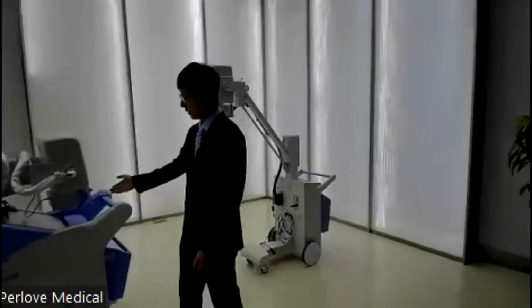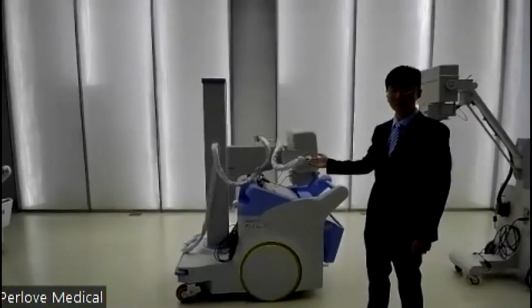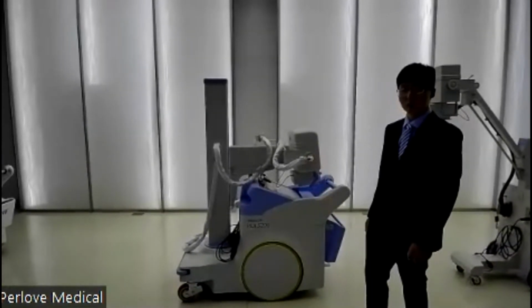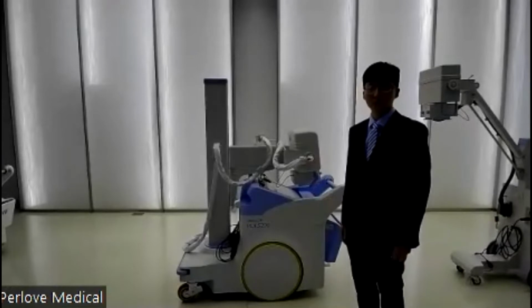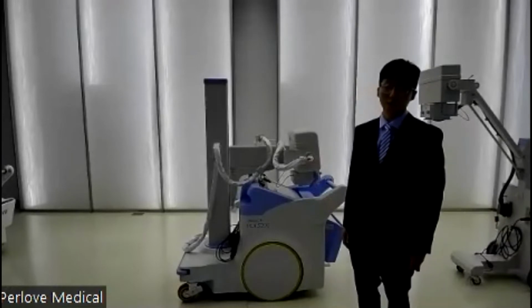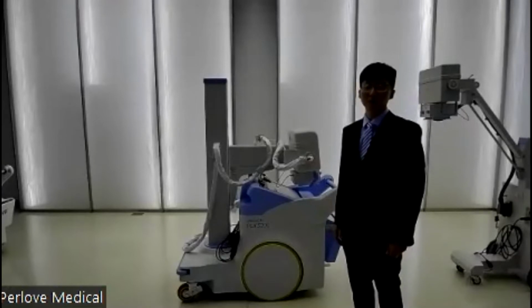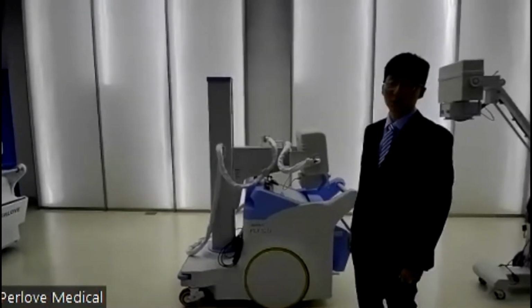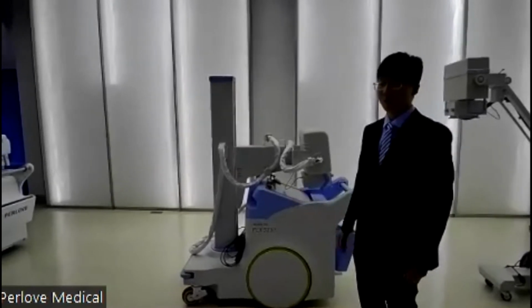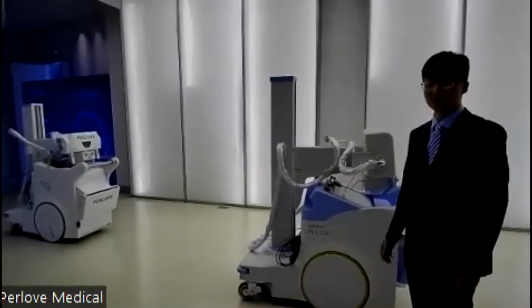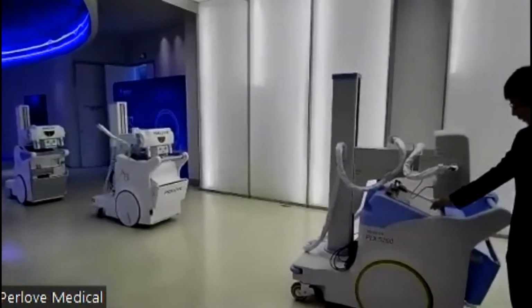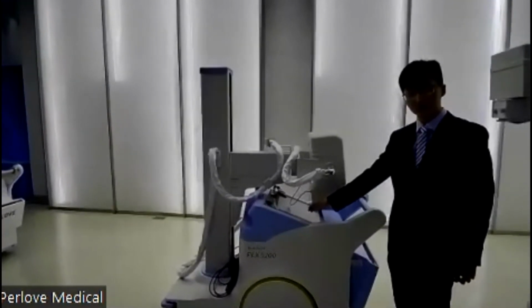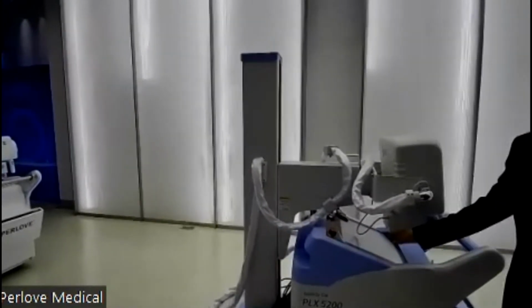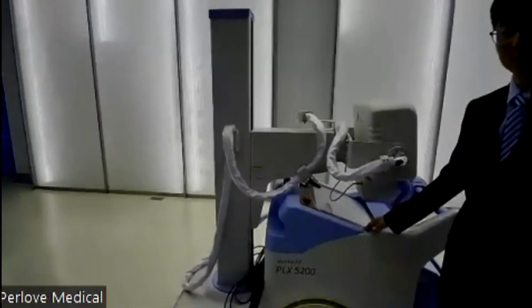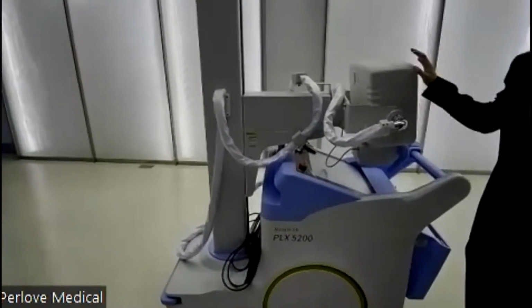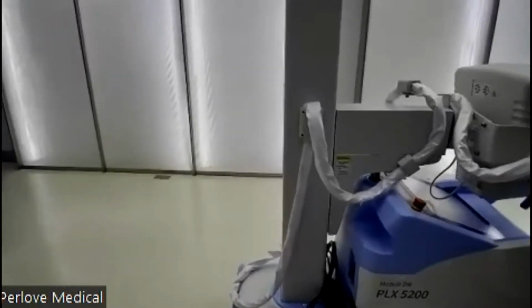Okay, now let's see this one. This is the PLX5200, 25 kilowatts. The output power is 25 kilowatts. The tube current is 200 milliampere. The size of flat panel detector is the same as the previous one, also 14 multiplied by 17 inch, but the specific parameters are better. And as you can see, the workstation is integrated with the machine. You can set the parameters and edit images with this, and it has multi-control, flexible movement.